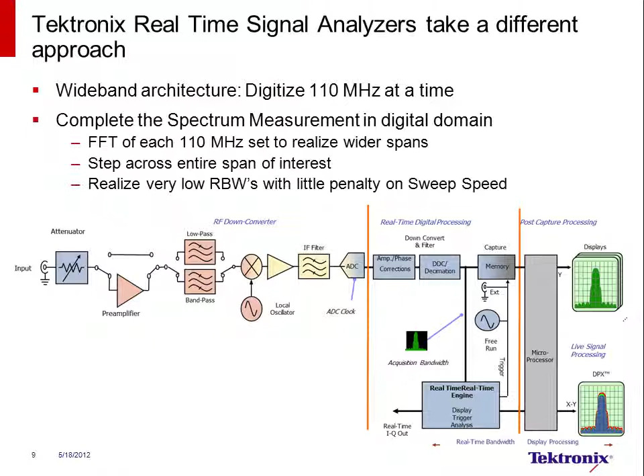The resulting speed for wideband spectrum measurements can be much faster when a low resolution bandwidth setting is required, because the instrument can perform an FFT across a much wider bandwidth of spectrum and display those on the screen. We will have one specific example of the improvement in sweep speed in the coming slides, but there is very little measurement speed penalty when using a narrow RBW measurement filter.